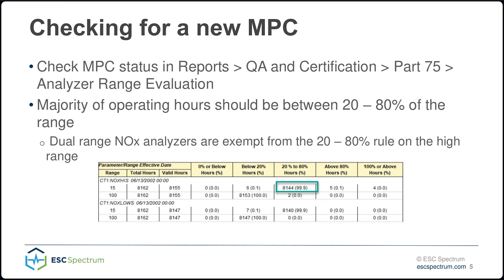I have my customers on a schedule that I do every year. In StackVision, I check the MPC status by going to Reports, QA and Certification, Part 75, and then selecting Analyzer Range Evaluation. From there, I view at least four calendar quarters worth of data. So if I'm doing it for a customer today, I'm probably going to do Q1 of 2023 all the way to Q1 of 2024. You should see the majority of operating hours between 20 to 80% of the range. If you have a dual range NOx analyzer, they're exempt from the 20-80 rule on the high range.